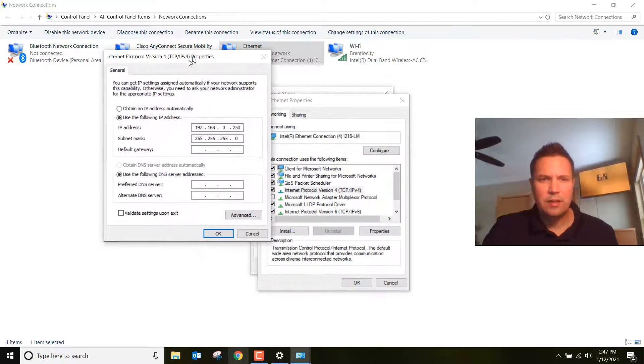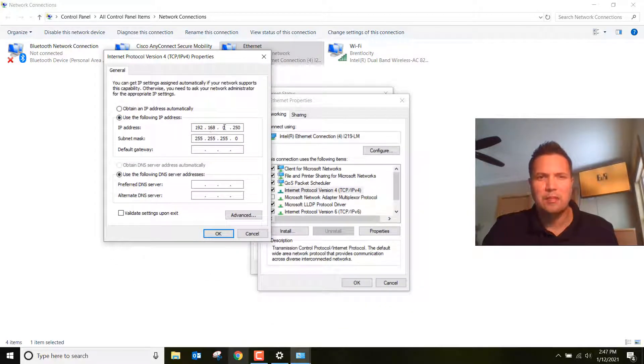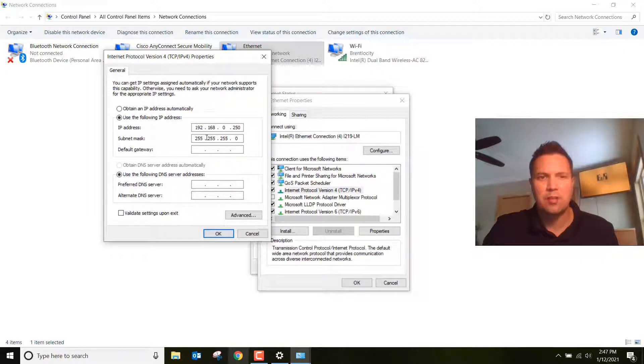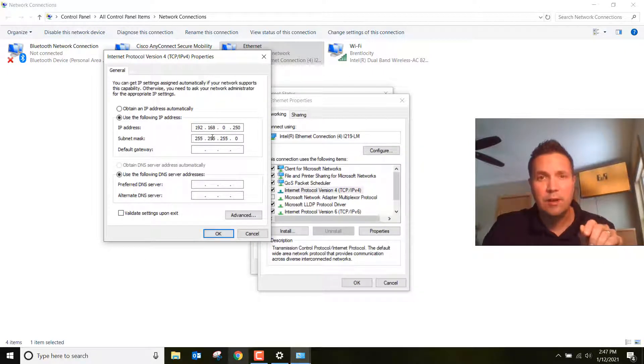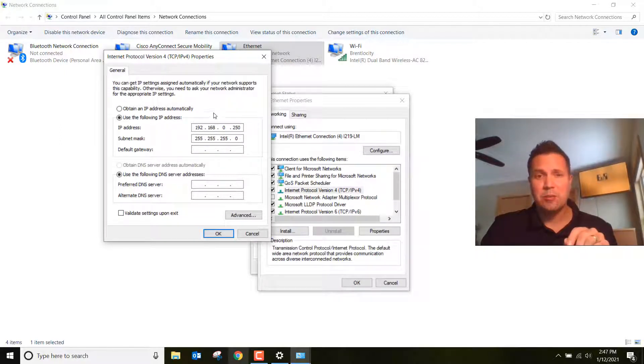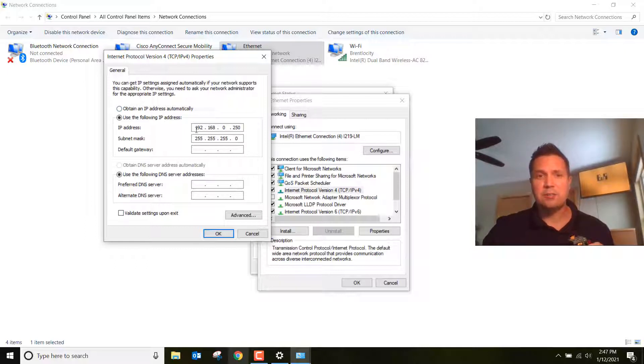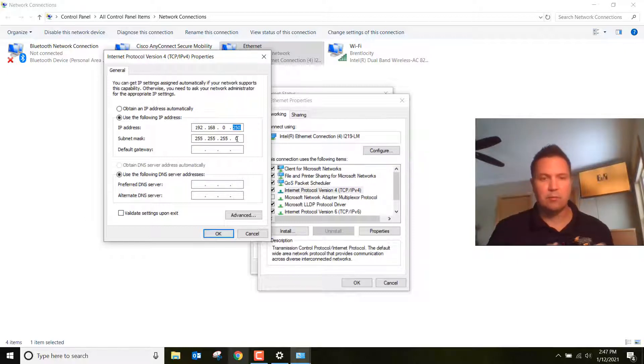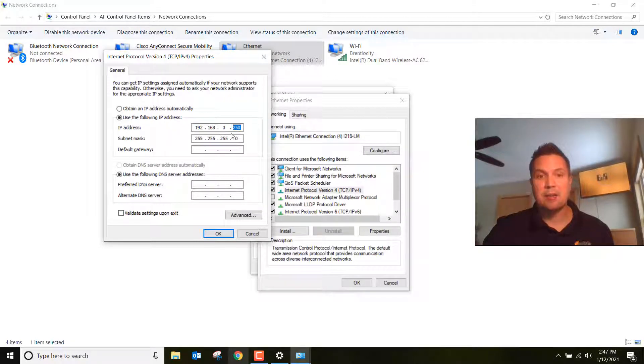Notice that you'll see our current IP address is 192.168.0.250 and the subnet mask is 255.255.255.0. It's very important that our IP address that we set for this controller is very close to this. These three digits need to be exactly the same, and then this last digit 250 needs to be slightly different for the controller. The subnet mask also has to be exactly the same. Make sure you memorize this IP address.